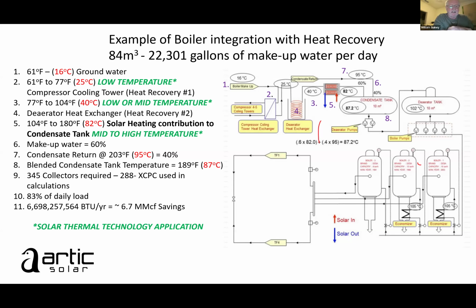In this case, it required 345 of our collectors. I only used 288 in the calculations because I typically don't size systems for 100% of the load. I prefer to size the system to about 70% of the load so we don't have issues with overheating. Because if their consumption of energy goes down or their water demand goes down, we end up with excess energy, and then we have to dump it to atmosphere or have overheating issues. So my preference is to design it a little smaller to be able to utilize every BTU we generate on an annual basis. So in this case, you can see we saved a significant amount of energy on this project by preheating that makeup water and blending it with the condensate return.